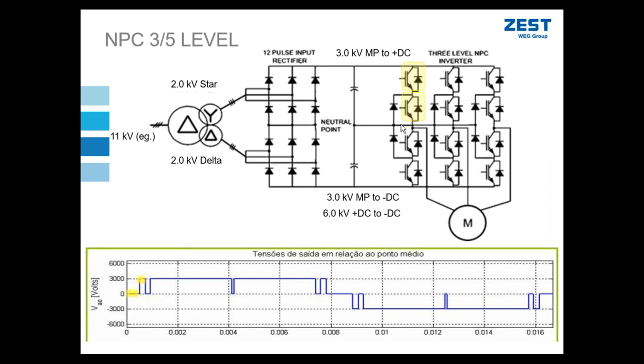I then transition from the two inside IGBTs to the two outside IGBTs. Notice that even though it looks like these IGBTs are connected in series, only one switches at a time. So I switch from my inside IGBT to my outside IGBT, and I'm now providing that full positive 3.3 kV phase to neutral. I then swing back to the inside, back to the outside, and so I can create a pulse width modulated phase to neutral voltage.